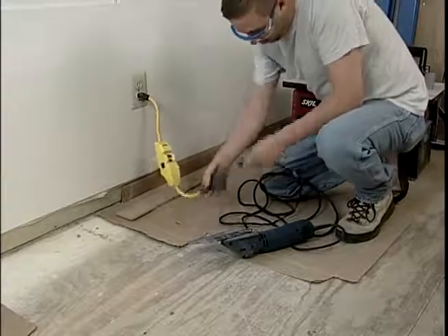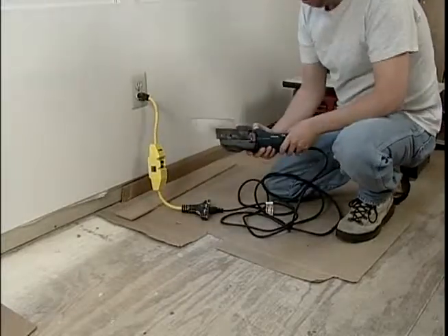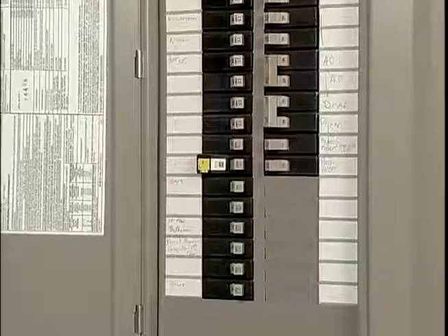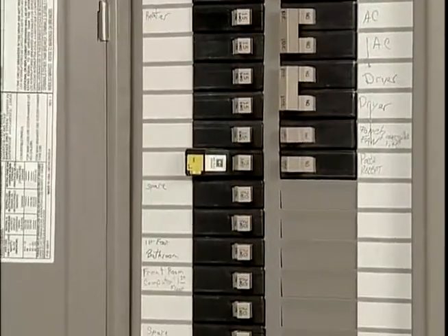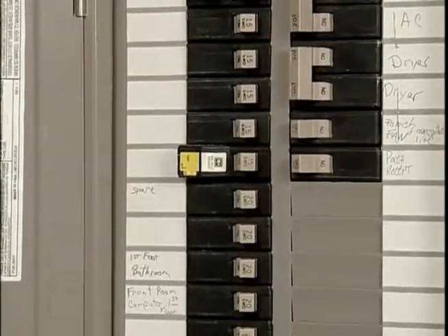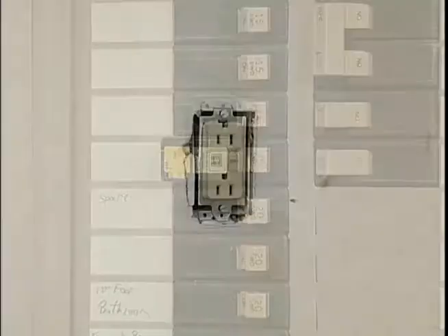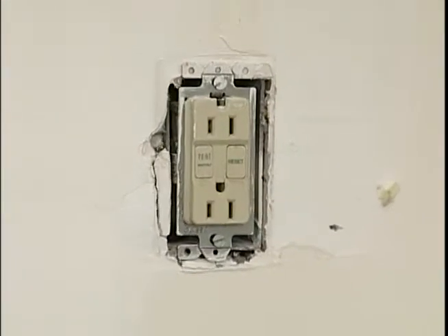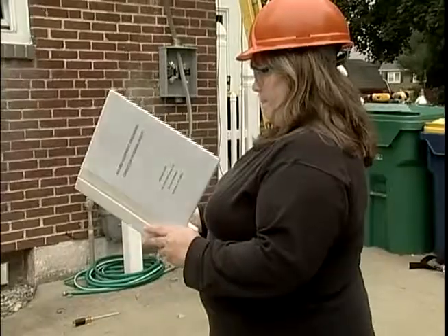As we've discussed, ground fault circuit interrupters also play a big part in electrical safety on construction sites. If possible, employers should have GFCI circuit breakers installed in all circuit boxes and cabinets that are not part of the permanent wiring of the structure that is being erected. Otherwise, GFCIs should be installed in all receptacle outlets.